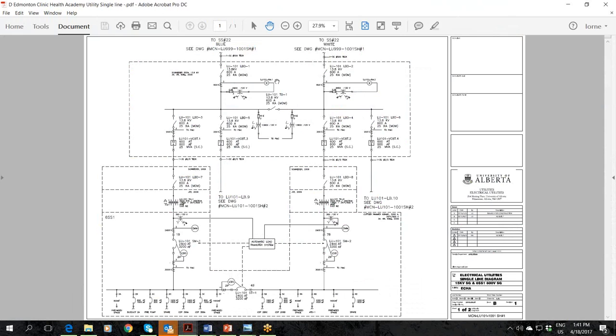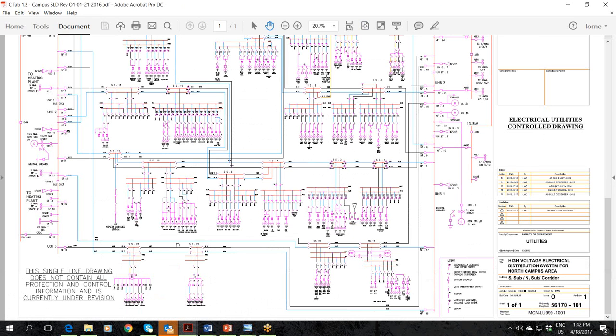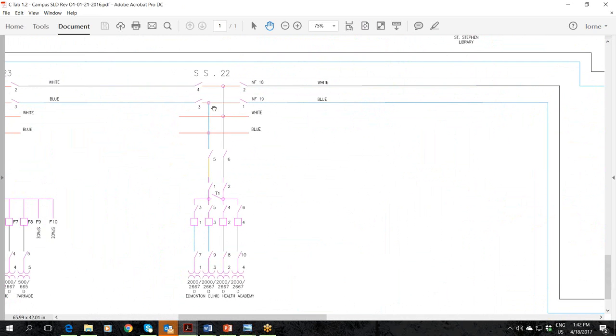Well, again, there are two different demarcation points. One where the cost of ownership starts and stops, and one for operation. The electrical utility is basically all us down to the building level. Once we get out of this sectionalizer, the building wall is around here. Okay, so when this building was built, the building had to pay for all this equipment. Yeah, right. From an ownership perspective, the building, which they call the buildings group, owns this, and if it needed to get replaced, they pay for it, just like they paid for it when it first got installed.